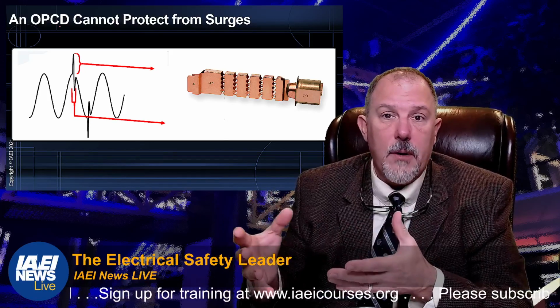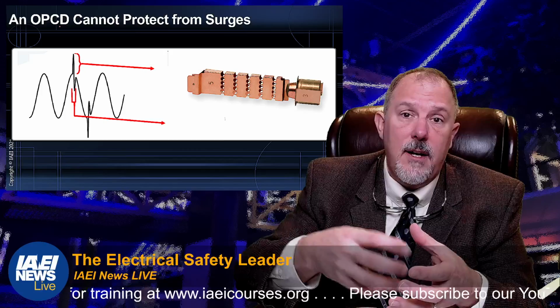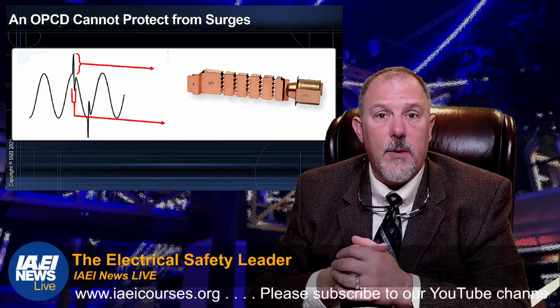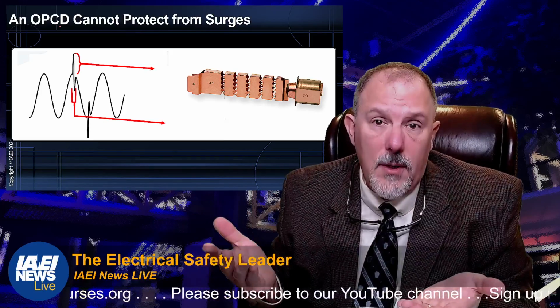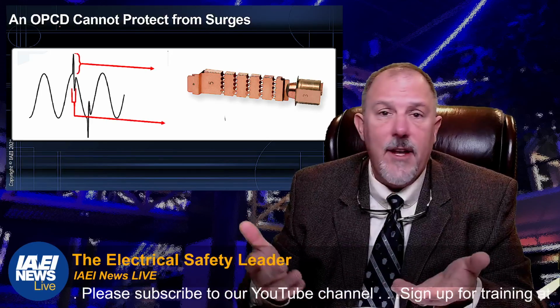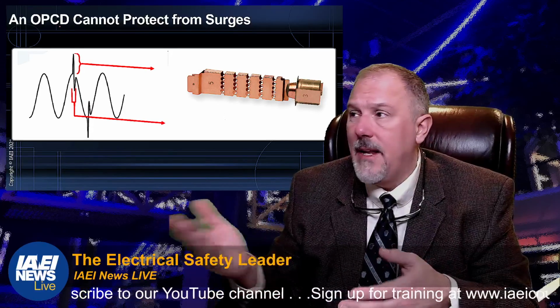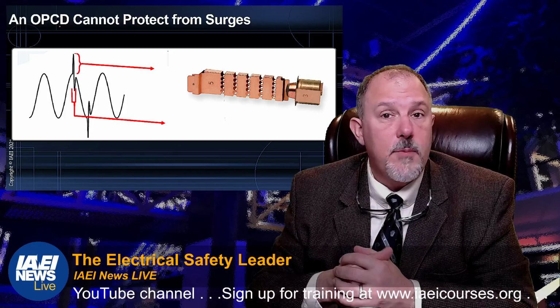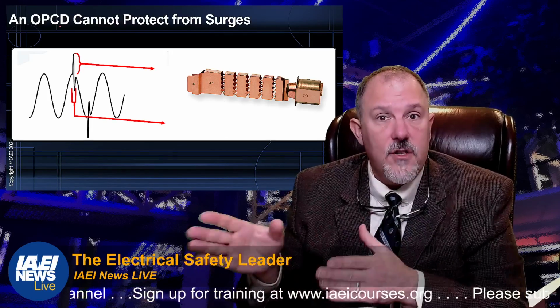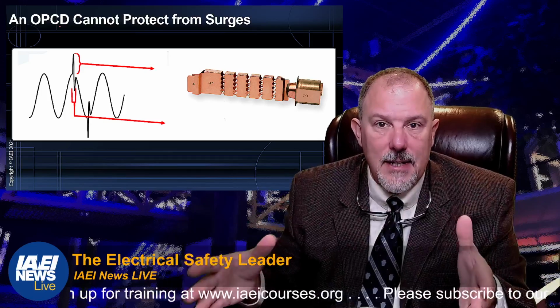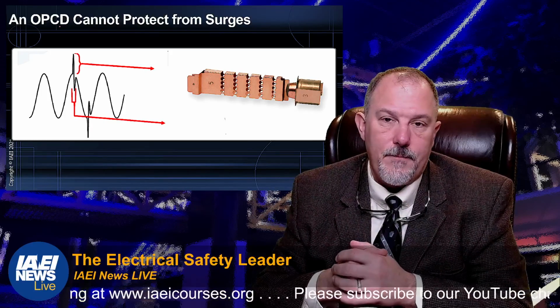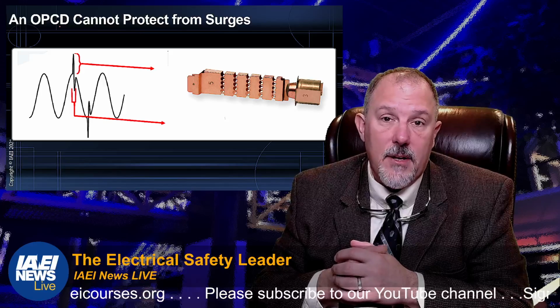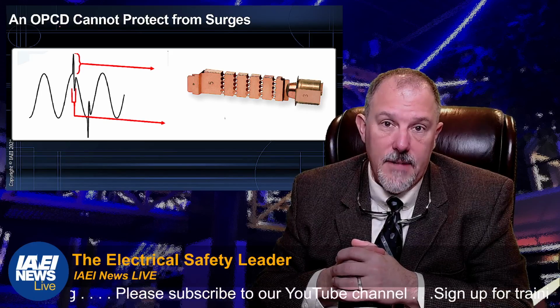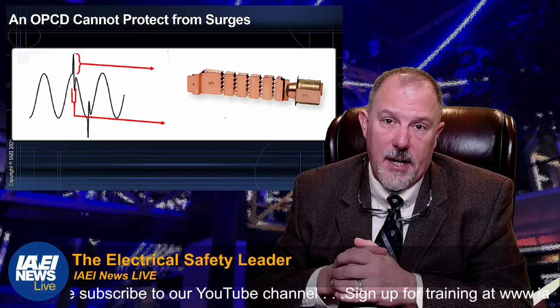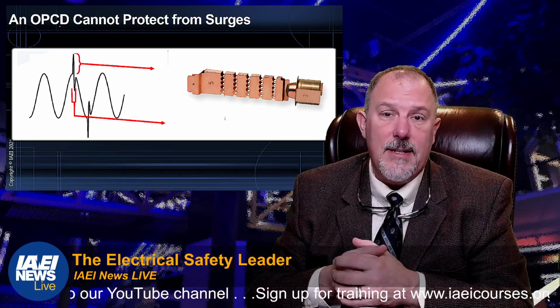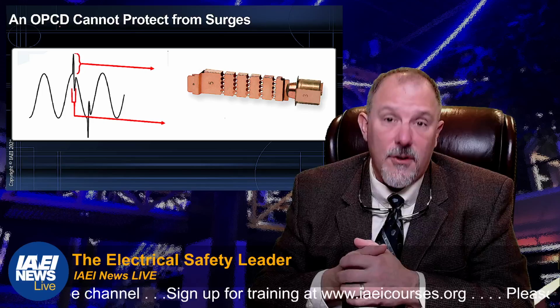Unless, now there are some circuit breakers out there where they've integrated surge into the packaging of the circuit breaker itself. So it does double duty. There are manufacturers who have a circuit breaker, say a 60 amp circuit breaker that you might have on a hot water tank, and it's got built-in surge protection. And it provides surge protection not just for the hot water tank, but for the entire facility because it's attached to the bus. But you're not getting it because of the 60 amp circuit breaker itself. There are receptacles that have built-in surge protection. There are power strips, multi-tap units that have surge protection built into them.